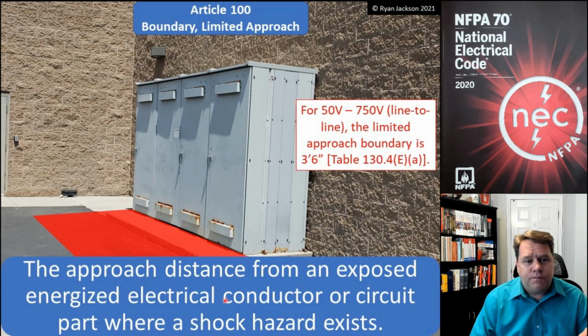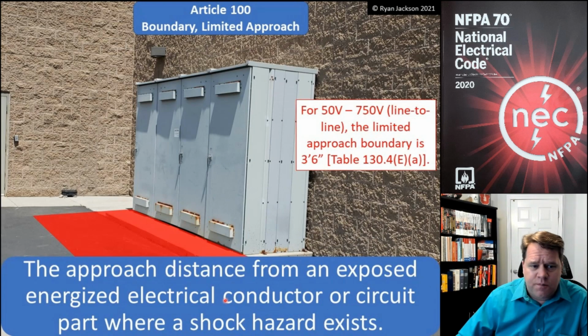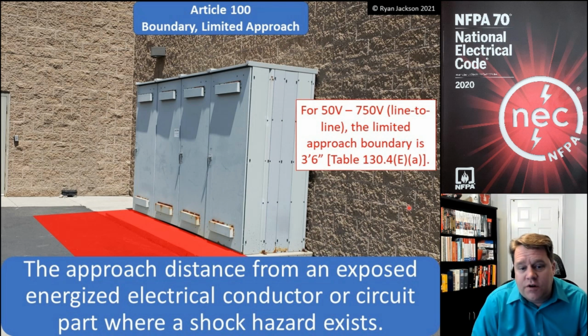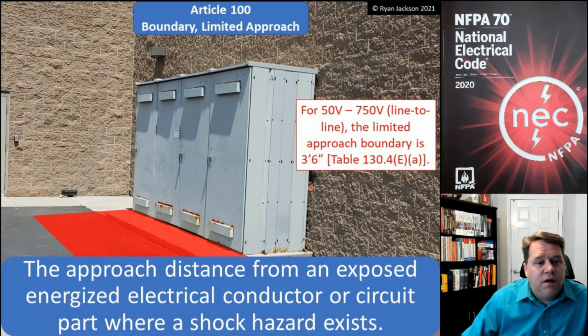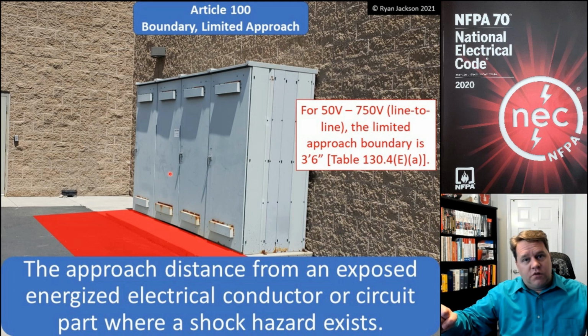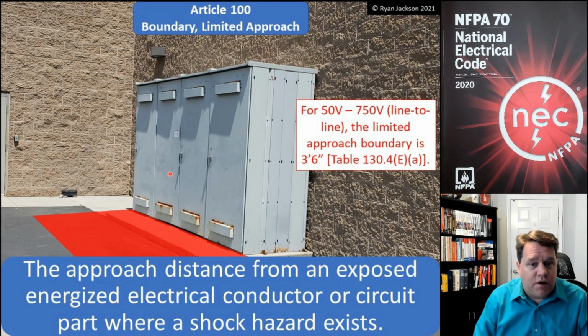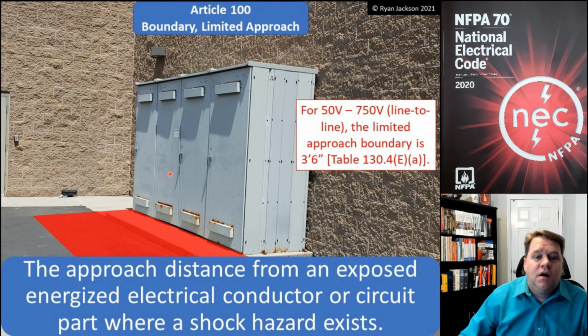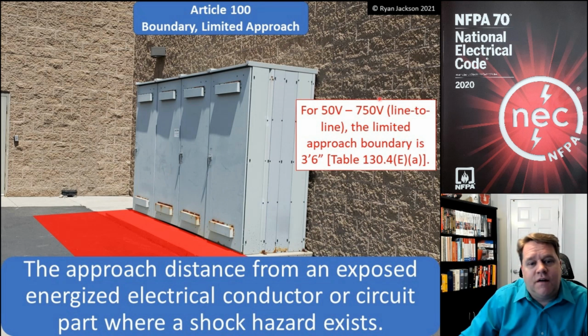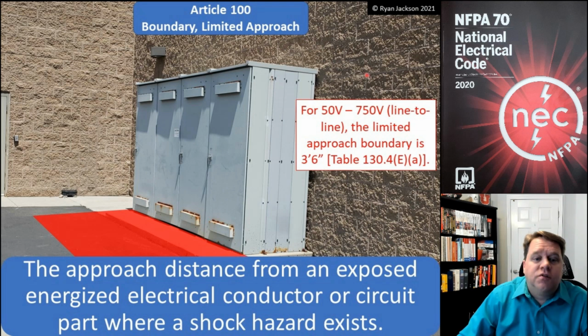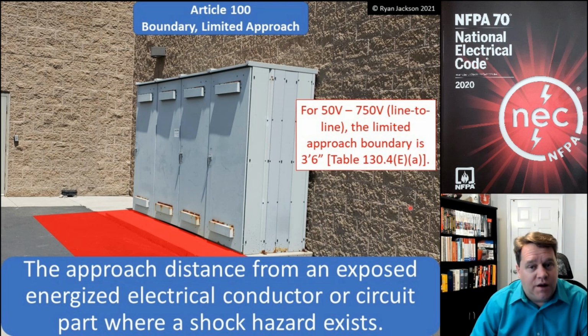Now, the definition of the limited approach is the approach distance from an exposed energized electrical conductor or circuit part where a shock hazard exists. Again, here in the photograph, the covers are closed. There is no limited approach boundary. But once I open those doors and remove any sort of dead fronts, then I have a shock hazard and I have a limited approach. So for 50 volts up to 750 volts line to line, the limited approach boundary is 3.5 feet.